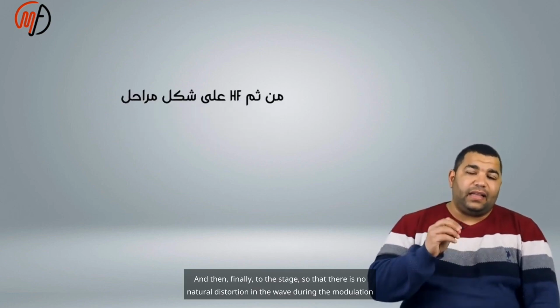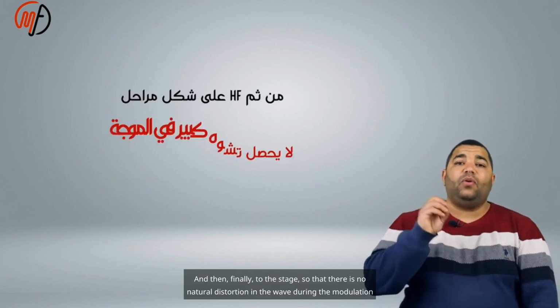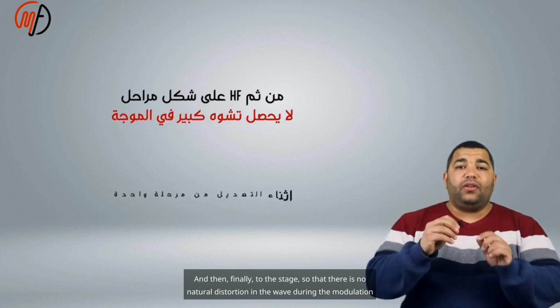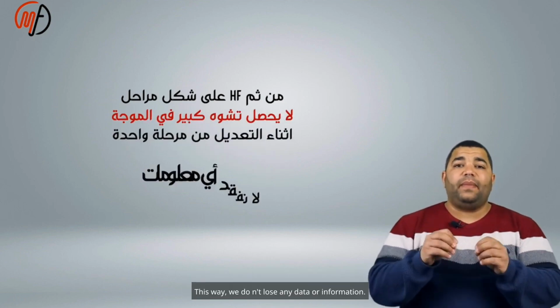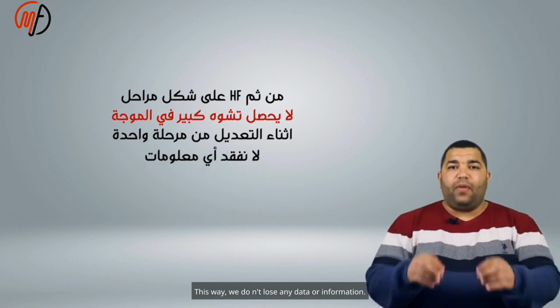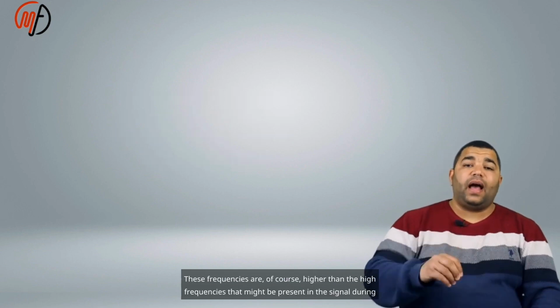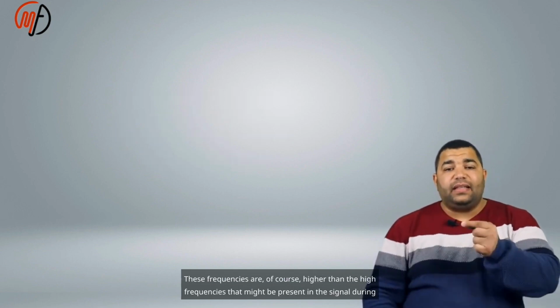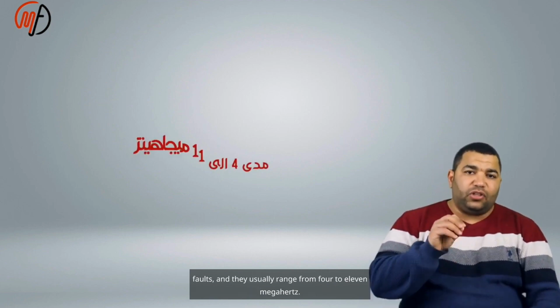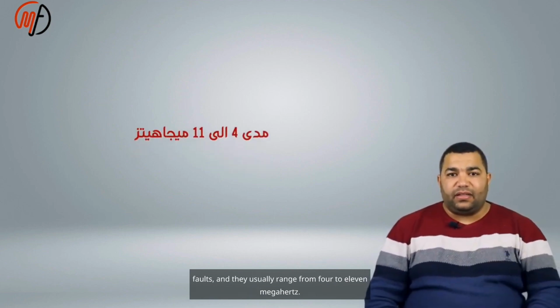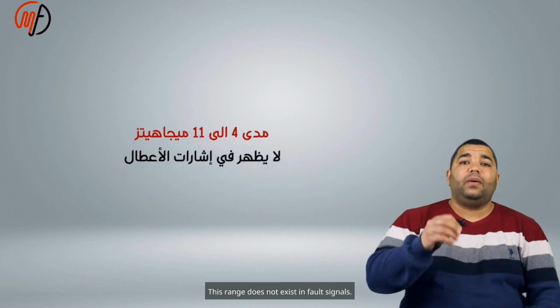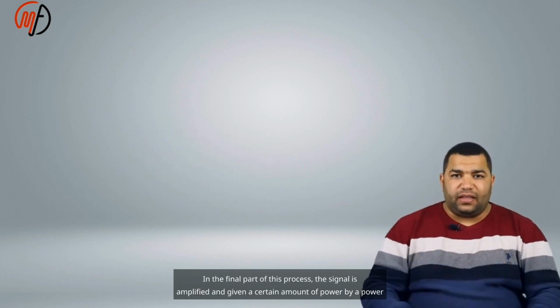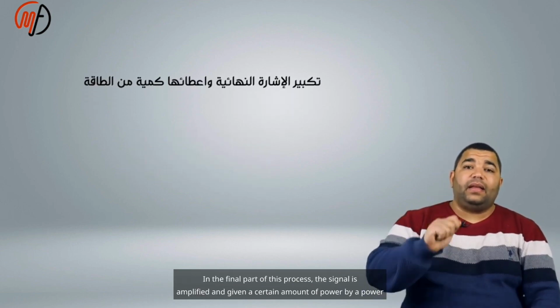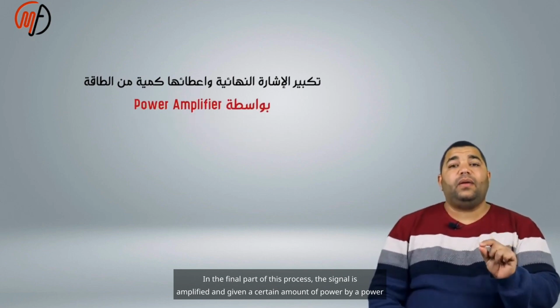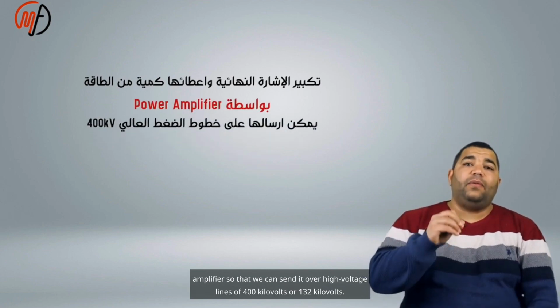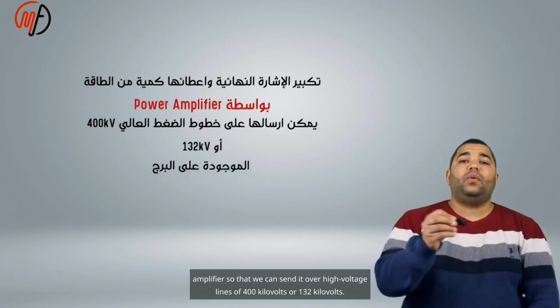kilovolts. This way, there is no natural distortion in the wave during the modulation from one stage to another, and we don't lose any data or information. These frequencies are, of course, higher than the high frequencies that might be present in the signal during faults, and they usually range from 4 to 11 megahertz. This range does not exist in fault signals. In the final part of this process, the signal is amplified and given a certain amount of power by a power amplifier so that we can send it over high voltage lines of 400 kilovolts or 132 kilovolts.